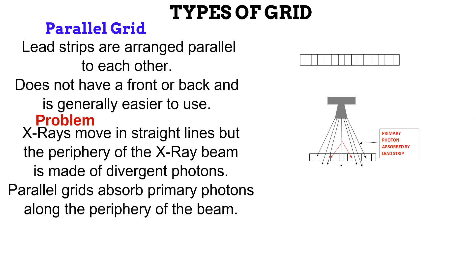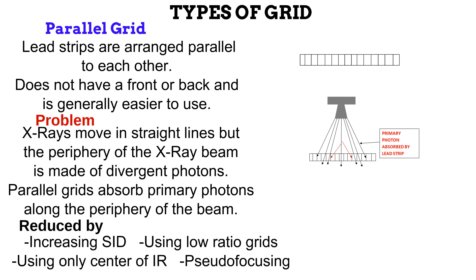This is because peripheral photons do not move in a straight line like photons at the center — they diverge, almost like how scatter diverges. The parallel grid treats these peripheral photons like scatter and absorbs them, producing geometrical cutoff along the edges of the image. This can be reduced by increasing the source-image distance, which makes the beam less divergent. Also, grids with a low ratio produce less peripheral geometrical cutoff than high-ratio grids, though low-ratio grids allow more scatter through to the image receptor. The effect can also be reduced by using only the center of the receptor, applicable in examination of small anatomical parts.